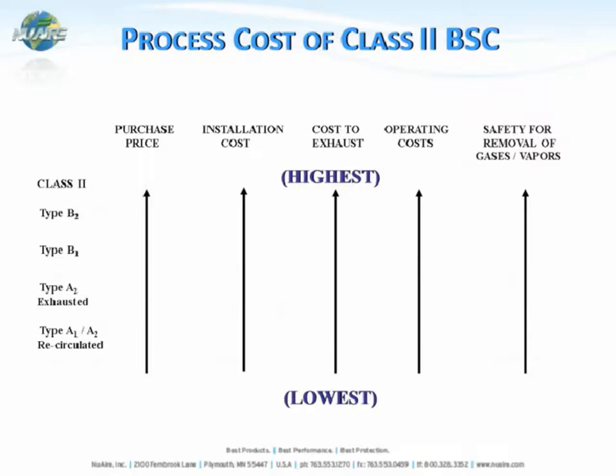Looking at the process cost of a Class II BSC, the lowest purchase price, installation cost, cost to exhaust, and operating cost — while also offering the lowest level of safety — would be a recirculated biological safety cabinet, like a Type A1 or A2. Costs rise as you move from A2 exhausted to B1 to B2, because you're exhausting much more of the air, and the initial purchase price and installation cost increase as well.